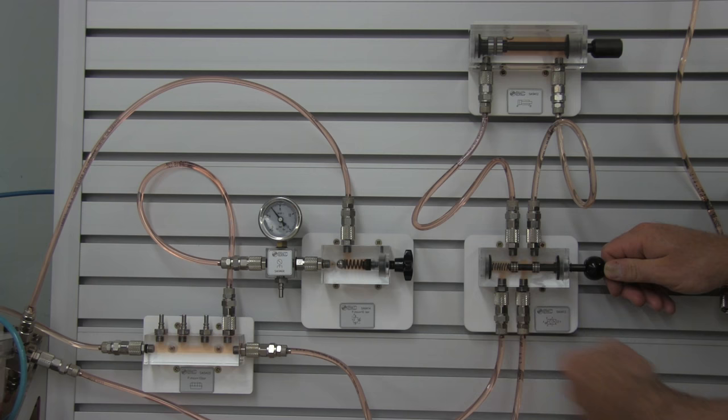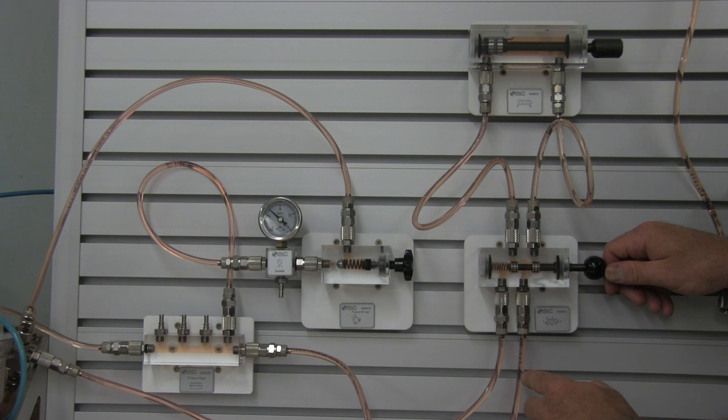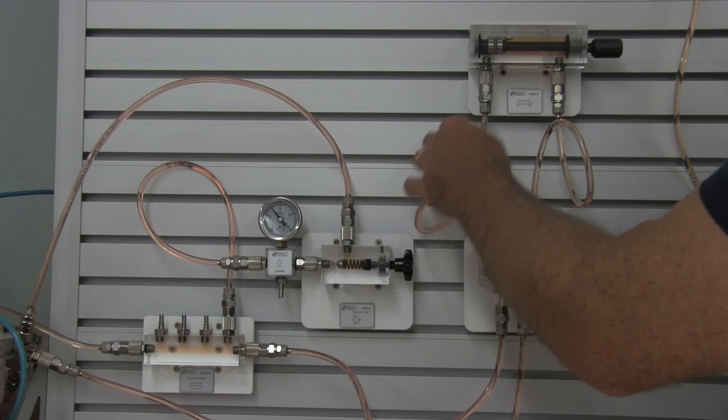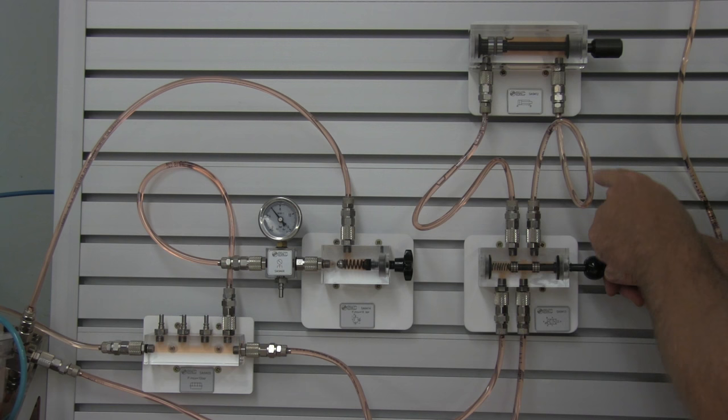You can see that the cylinder extended out and it retracts. So when I press my lever here, the pressure that's coming from my pump is being connected to my A port of this cylinder. My B is being connected back to tank, and this oil is allowed to drain out.